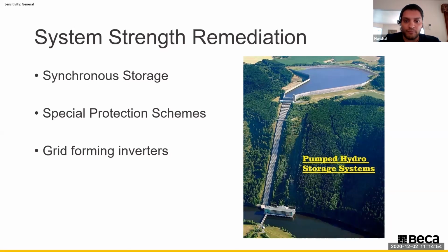Another option which is becoming more common is grid forming inverters, which aim to replicate the function of synchronous machines through synthetic inertia. In Australia, there have been a couple of cases, particularly in South Australia, where they've trialed grid forming based inverter systems using synthetic inertia to prop up system strength. It's very common amongst island network arrangements, and as a system strength remediation solution, it's becoming more common as more inverter-based generation is introduced onto the network.